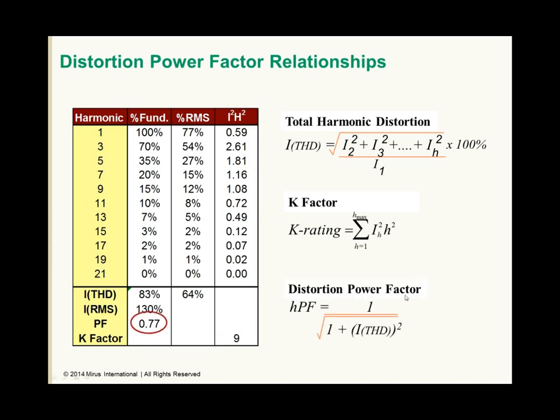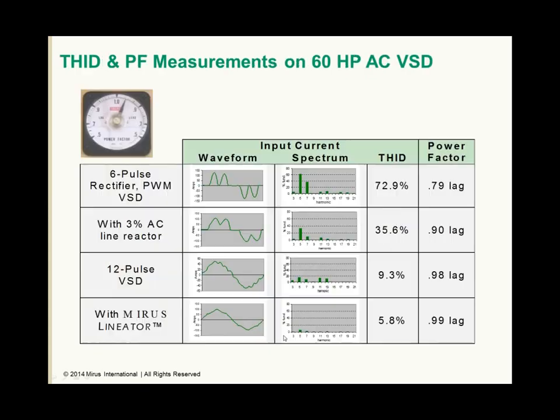And then our power factor, in this case, is the distortion power factor component. So it's a component that's introduced by the harmonics, is equal to 1 over the square root of 1 plus the total harmonic distortion squared. So in this case, it's 0.77. So we have a very low power factor, and this very low power factor is due to the harmonics introduced by the nonlinear load. To show this in another way, I've got some waveform representations of 4 different types of loads.